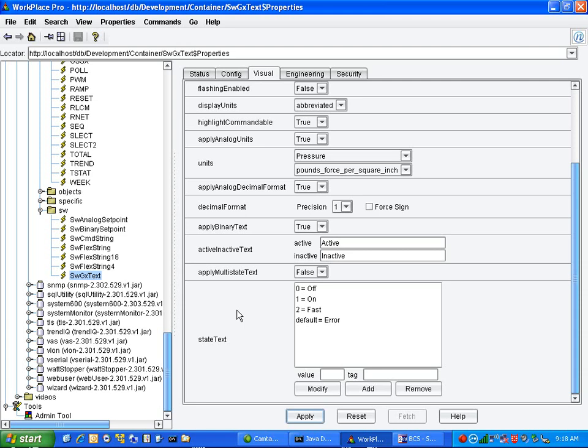It will not pass. If I set that object in the UNC to be 3-4 decimals, and then I link it directly externally, it'll by default give me just 2. So I have to turn it back to 3 or 4 on the other end to get that to display. But it will display. It will pull it out of there, if you get it right.